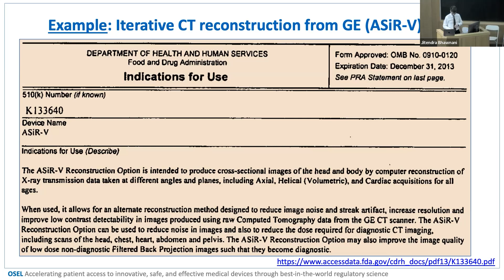And at that moment, manufacturers had an interest in having quantitative dose reduction claims in their labeling for the FDA. Eventually, after a lot of work by companies and FDA and others, it was accepted. It's part of the public summary. In this case, for example, this particular iterative reconstruction can have a dose reduction of 50 to 82%, low contrast detectability improvement of 59 to 135%, spatial resolution improvement up to 100%, and things like that.